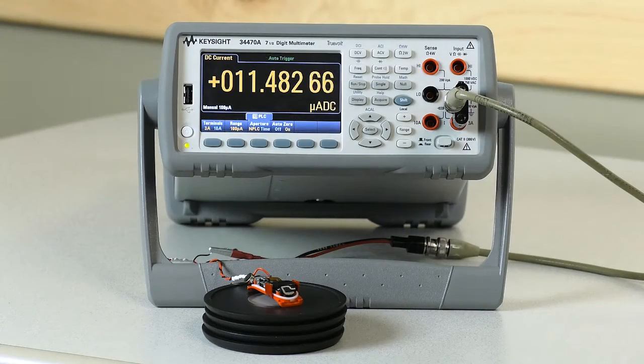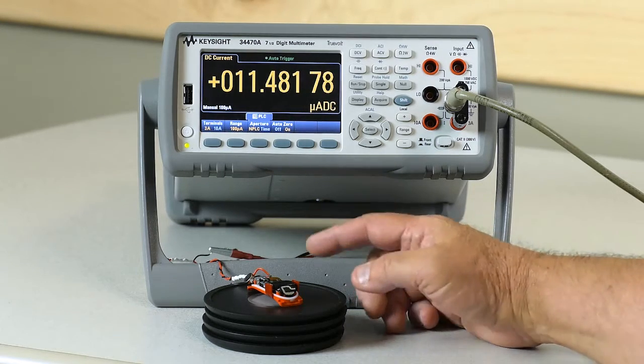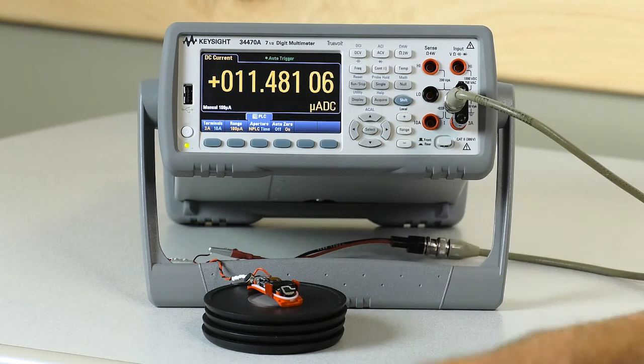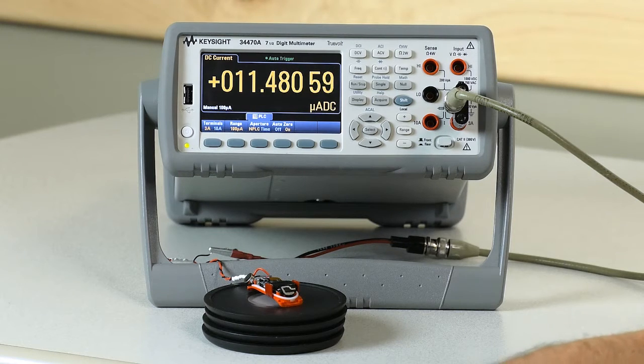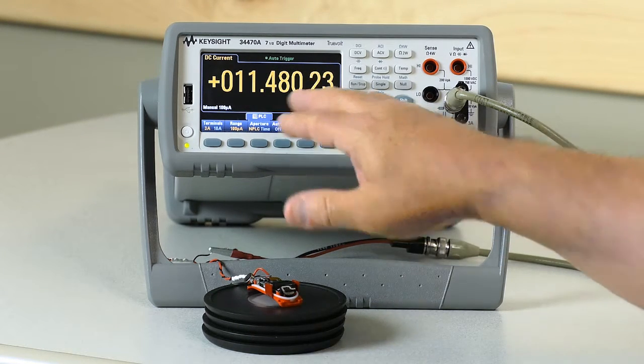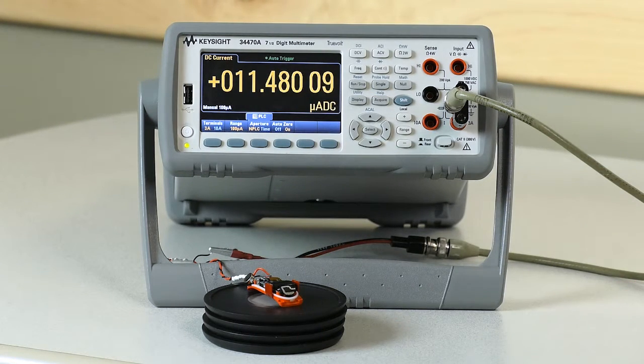Here we have the device under test, in this case a wearable fitness monitor connected to the 34470 digital multimeter in a conventional mode. We can measure the resting current at 11.4 microamps.